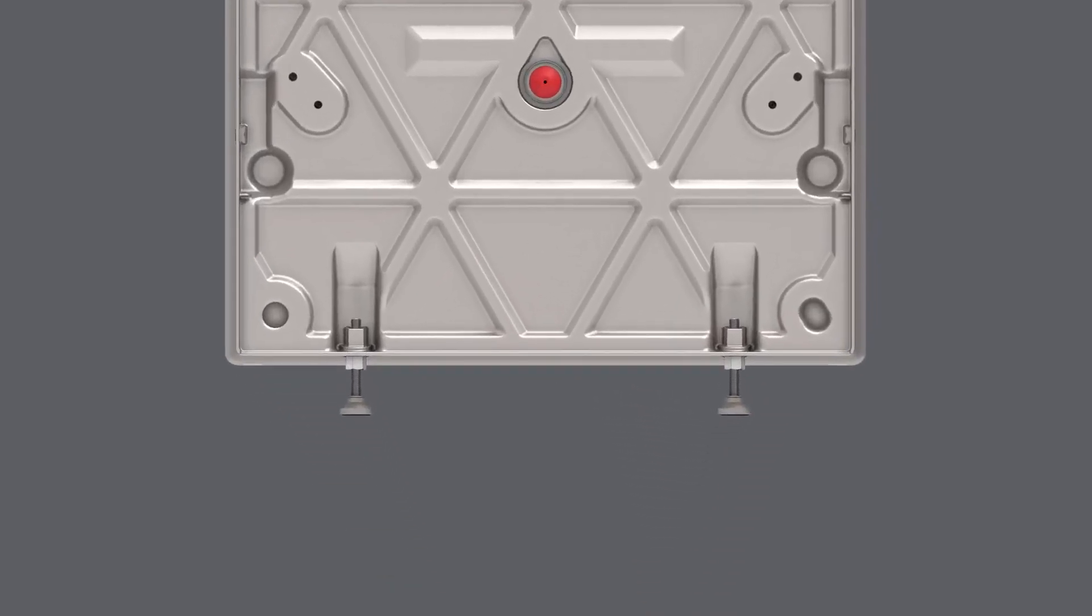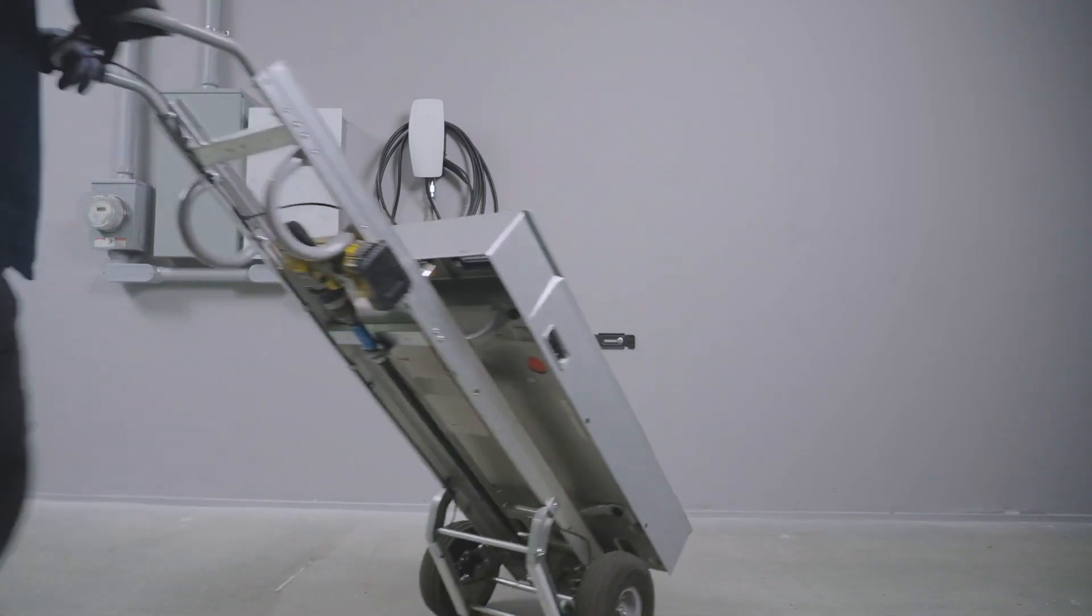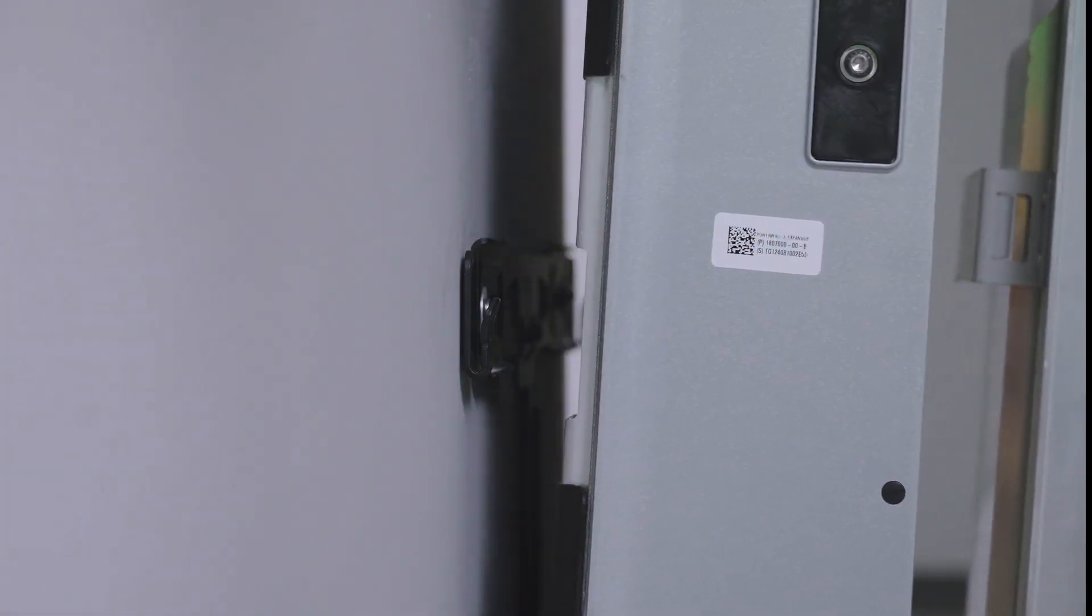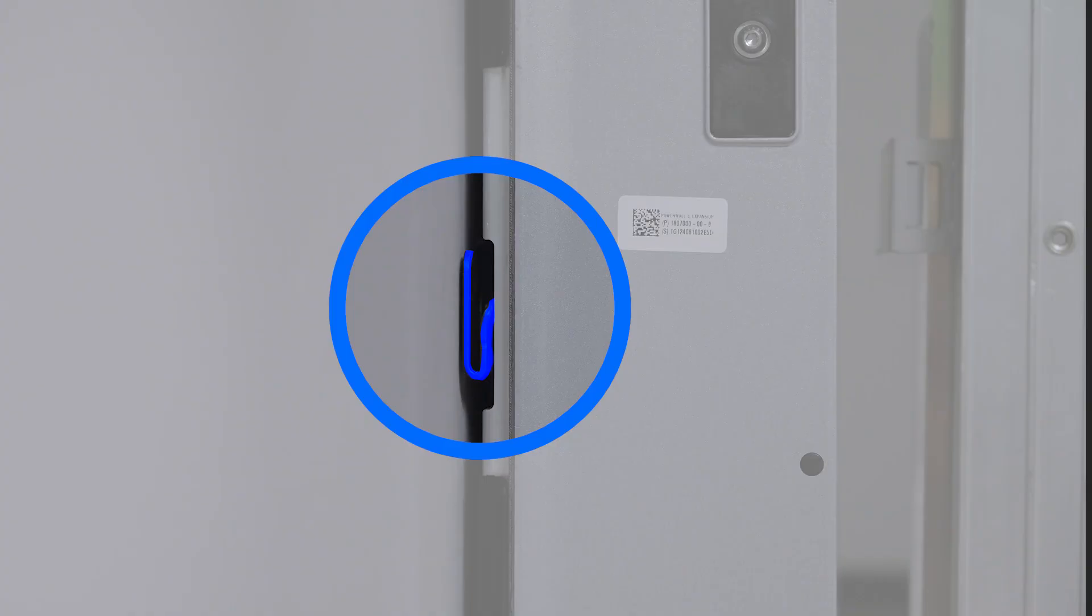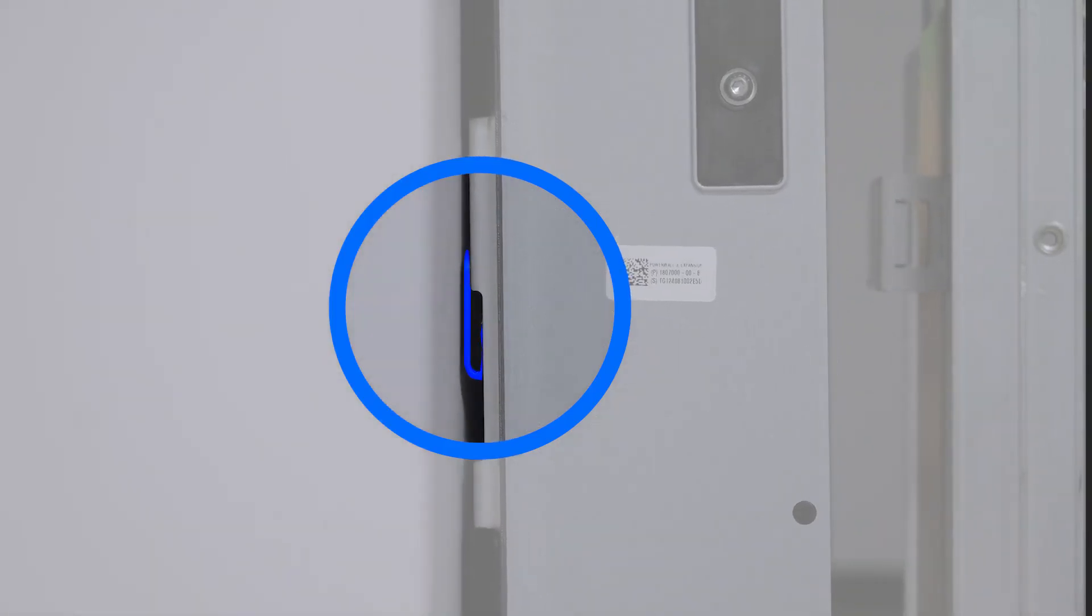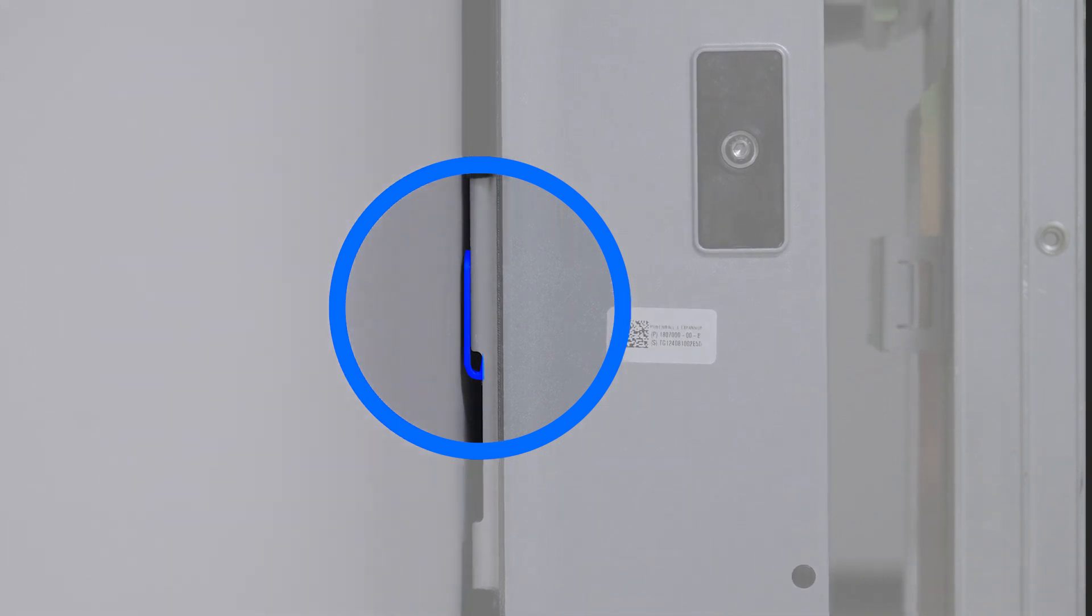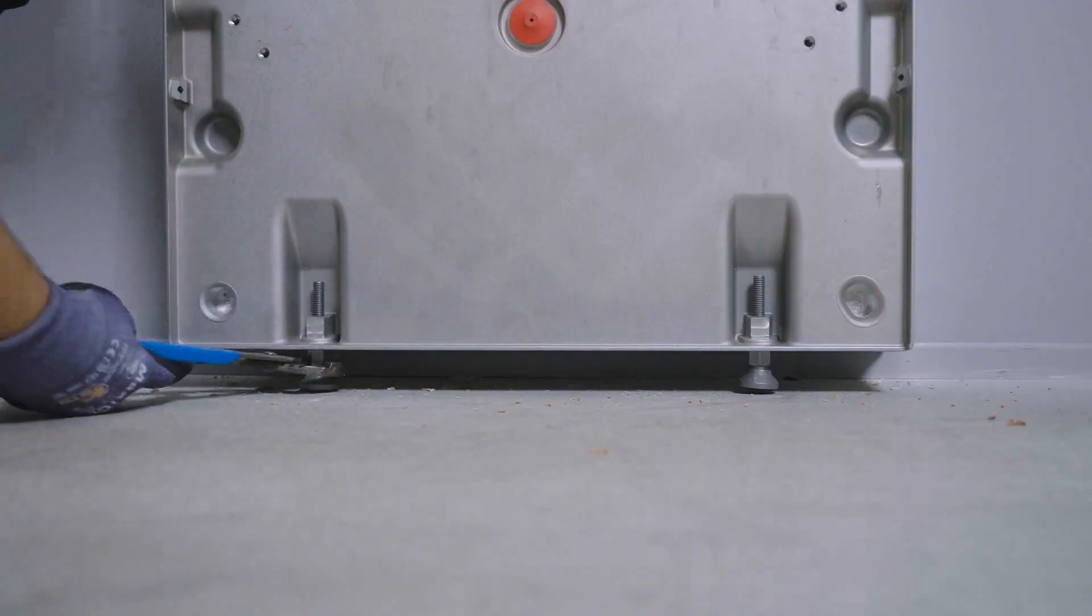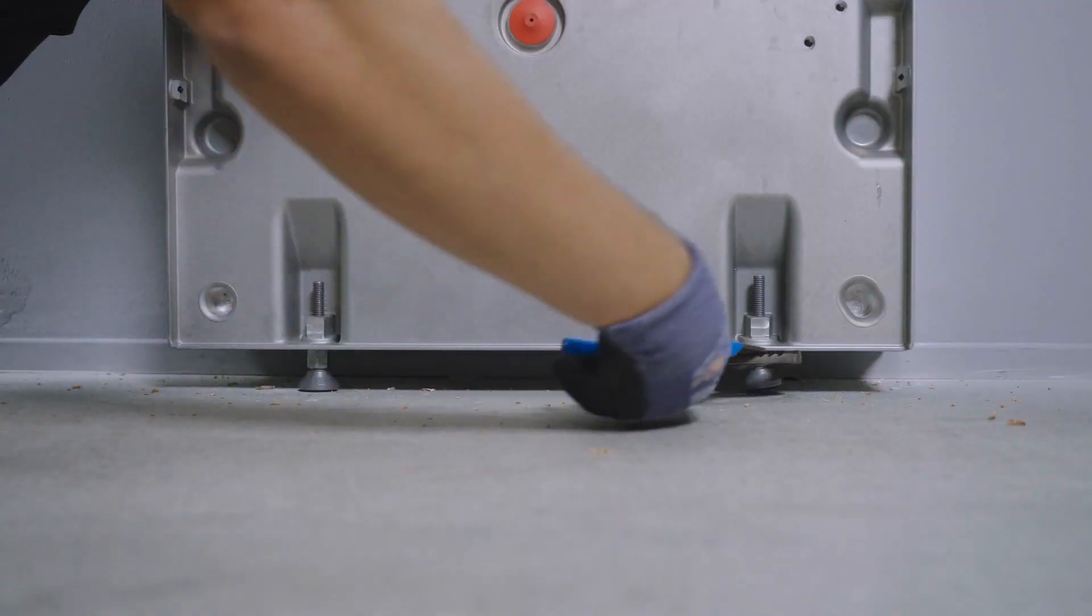For the unit mounted to the wall, ensure that the leveling feet start all the way up. Use Powerwall dolly to position the Powerwall 3 expansion so the mounting cleats are just above the flanges on the bracket. Lower the unit until both the upper and lower sets of cleats engage the flanges on the bracket. Visually confirm that all four cleats are engaged on the mounting bracket before proceeding. If needed, adjust the leveling feet so that both are resting on the floor.